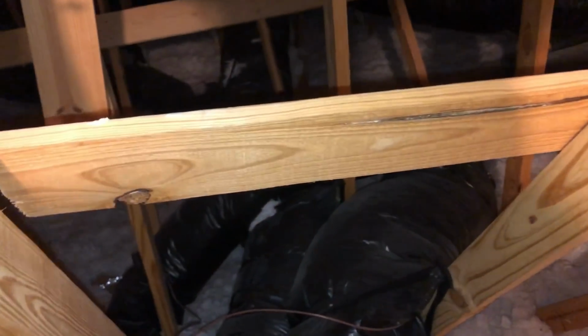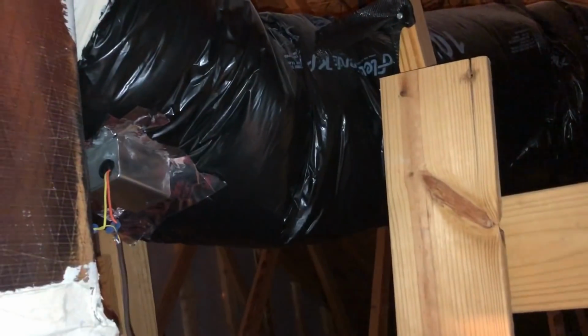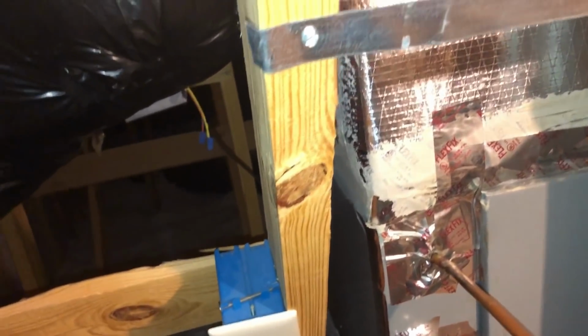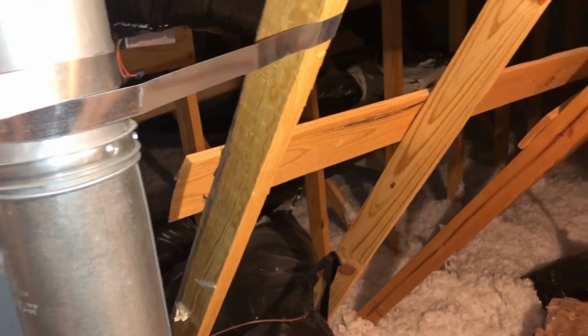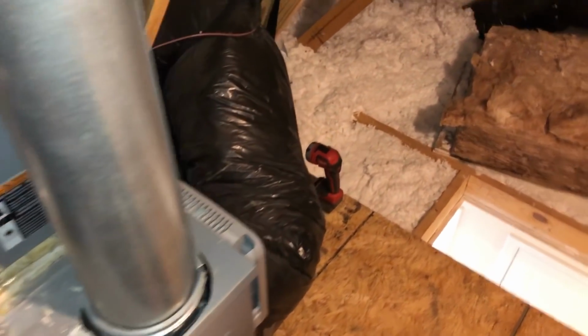And this dang zoning, I tell you, I just don't get it. When they put this zoning on a single stage piece of equipment, it just doesn't work. And, you know, I don't see a bypass. I see 3 zones. There's 1, 2, and 3, and I'm not a fan of a bypass at all. I think it's a joke. All it does is relieve the blower. Doesn't do anything else. But there's not one on this. So if the smallest zone is ever calling by itself, boy, that's just not good.